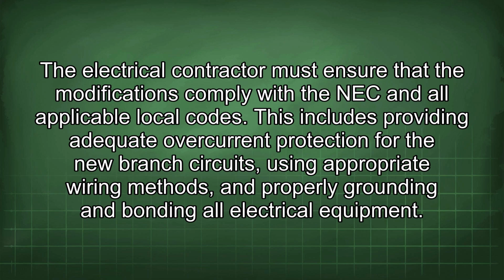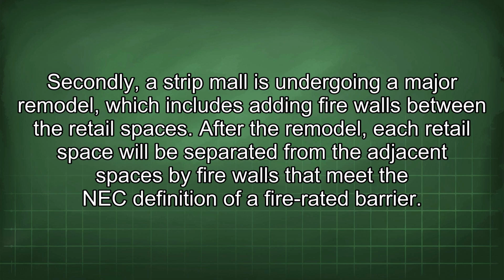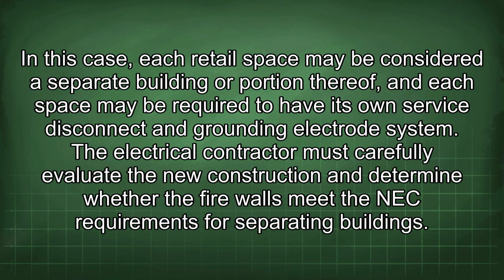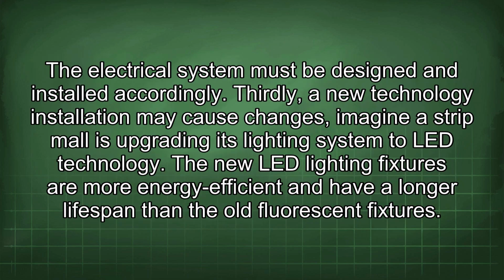all electrical equipment. Secondly, a strip mall is undergoing a major remodel, which includes adding firewalls between the retail spaces. After the remodel, each retail space will be separated from the adjacent spaces by firewalls that meet the NEC definition of a fire-rated barrier. In this case, each retail space may be considered a separate building or portion thereof, and each space may be required to have its own service disconnect and grounding electrode system. The electrical contractor must carefully evaluate the new construction and determine whether the firewalls meet the NEC requirements for separating buildings. The electrical system must be designed and installed accordingly.